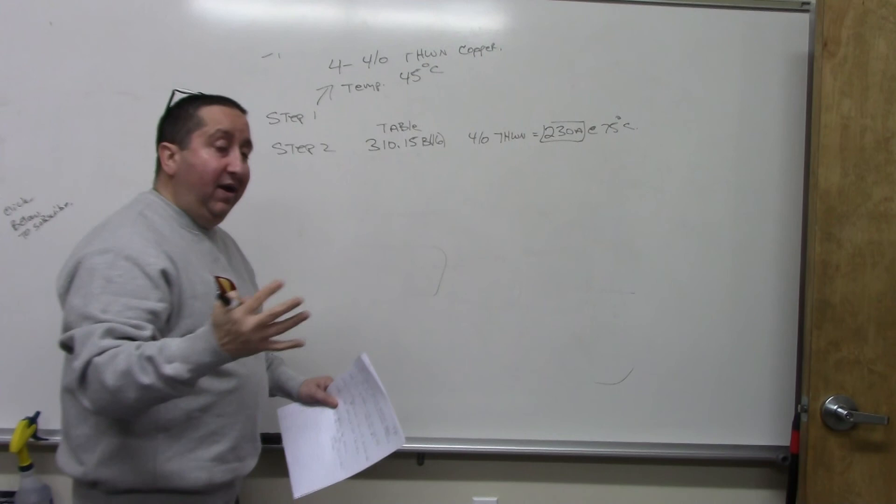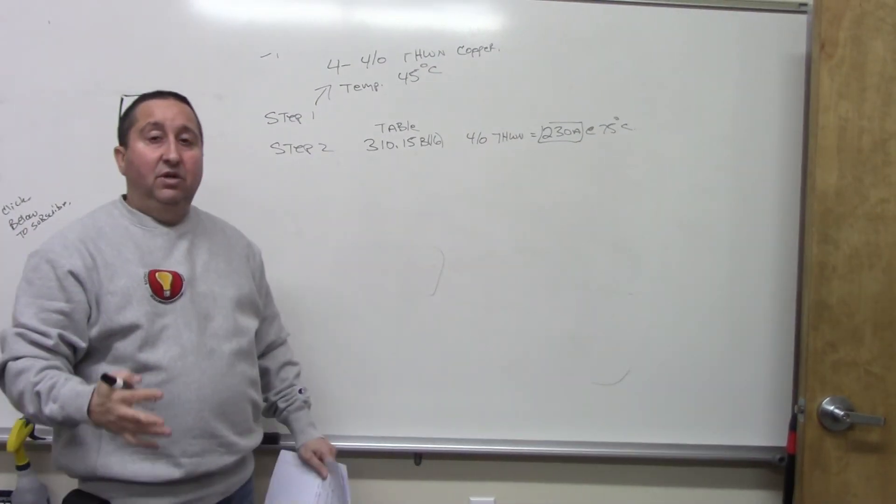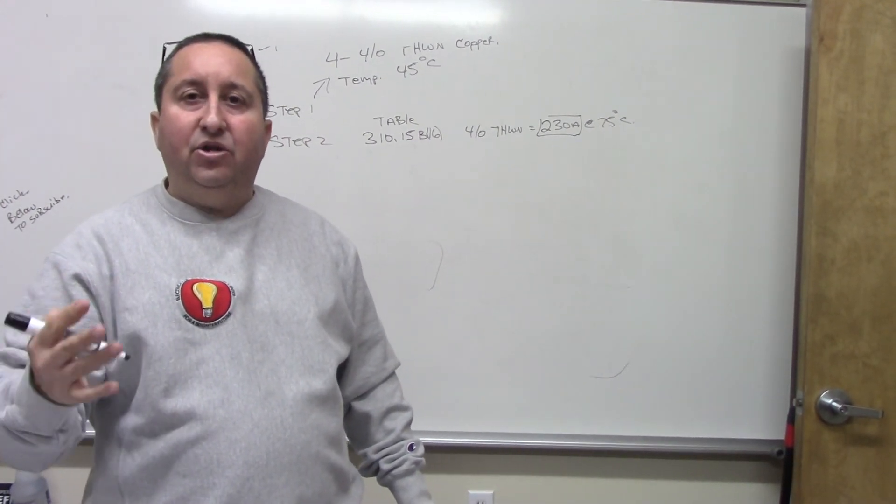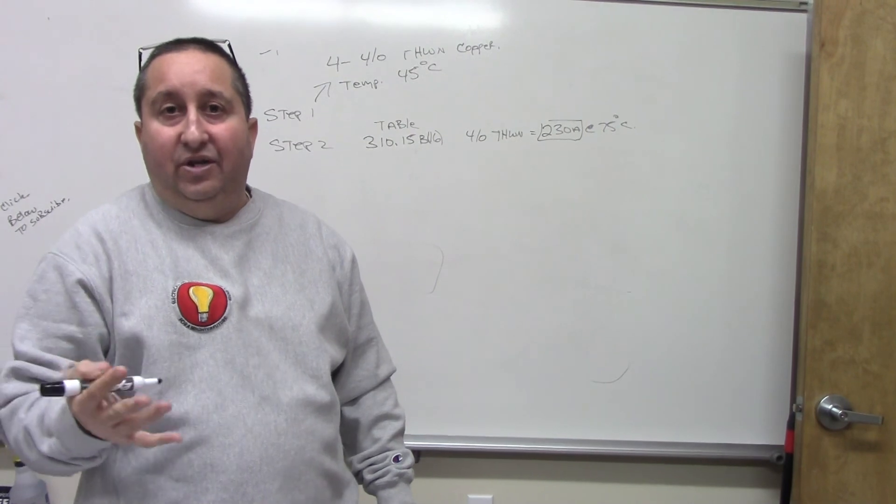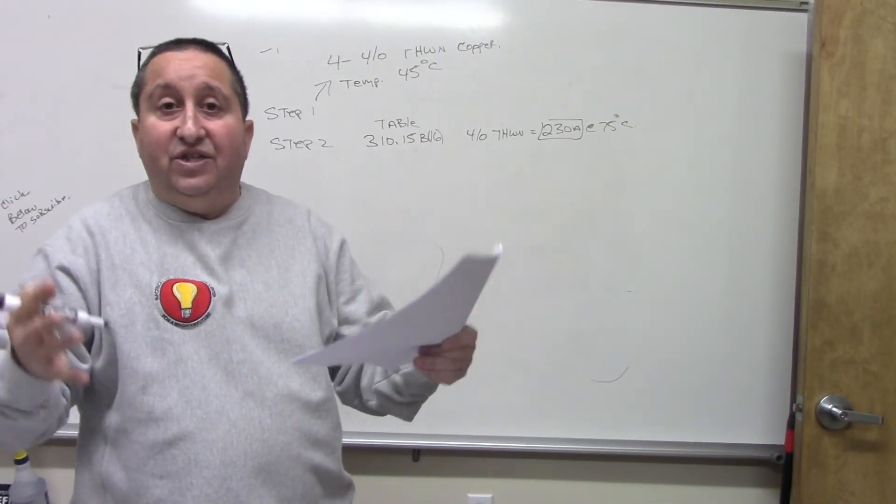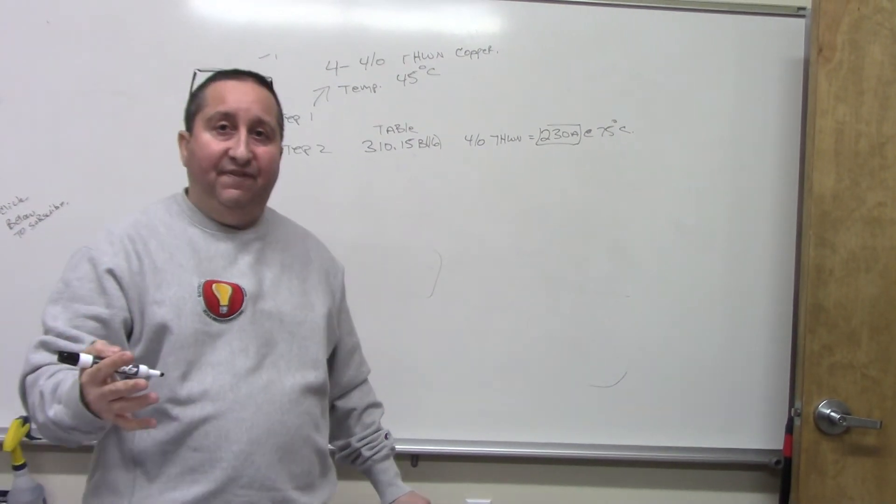But the problem is, we have four current carrying conductors. Once you put ampacity on a conductor, you're creating heat. That's what ampacity is - basic foundation, it's just heat. So since you have four, you're creating heat, so there's an adjustment factor.